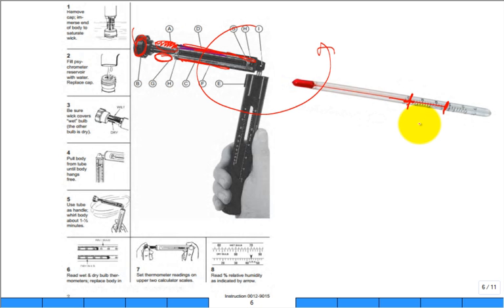And so now, if somebody like a technician comes into this room, somebody says, I'm hot and stuffy in this room. They used to take out some device like this. Now it's all electronic. But they would sling it around, and then they'd pull it down, and they'd say, okay, I know the dry bulb temperature. Oh, it's 75 degrees F in here. And I know the wet bulb. Oh, it's 62. And they would tell how much humidity is in the room. And built into this, there's a little scale right here. You put the pieces together, you slide the scale, and you can actually infer the relative humidity.